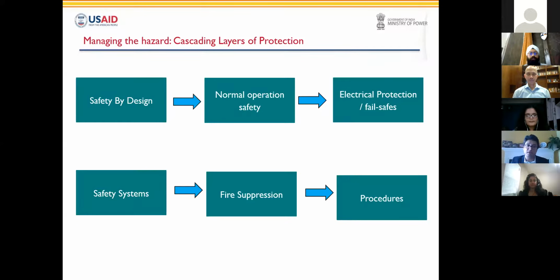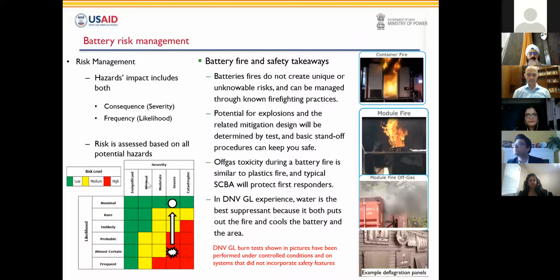Just from our experience, in the event of a container fire, the recommended strategy is to let the fire burn out and contain the fire through water sprays from a safe standoff distance. Do not open or enter the container without prior approval of the project safety expert. Again, this slide has some fire and safety takeaways obtained from our experience of burn testing and suppressing battery fires. I won't go into this slide in detail, but the general idea is follow the safety by design philosophy, and all these requirements are encoded in the latest safety and thermal management standards.